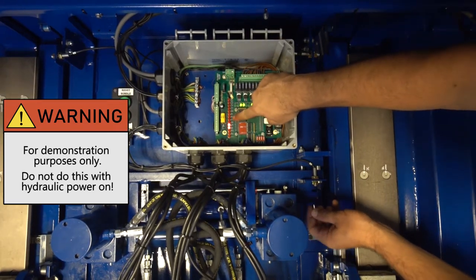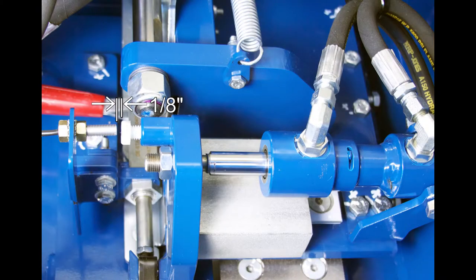All these reed switches should be adjusted to have a 1/8 inch air gap between them and their magnets.